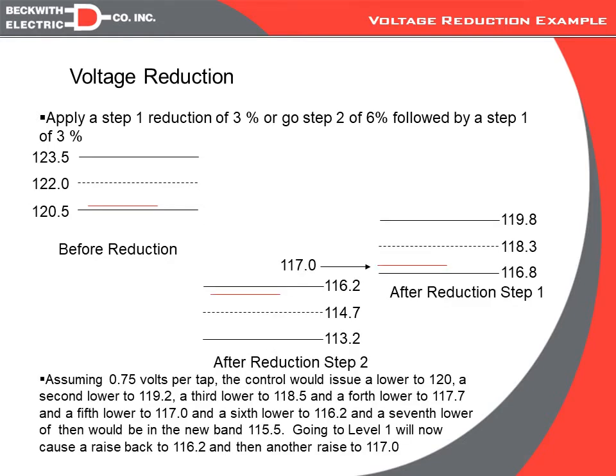Now, what if we were to do a 3%, but instead of just doing a 3%, we will start with a 6%, and then we will follow it by a 3%. So ultimately, we're going to finish up at 3%, but instead of just starting with 3, we're going to start with 6%. Well, if we do a 6% reduction, our new band center becomes 114.7, and starting the voltage out here and going 3/4 of a volt per tap, ultimately we have to get lower than 116.2, and we'll finish up at 115.5.